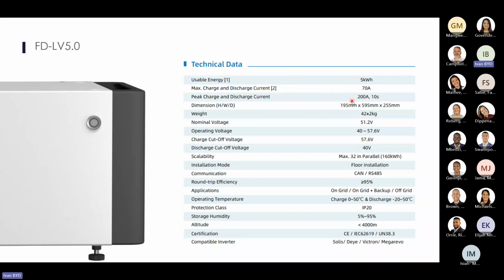So that means on your low voltage batteries, typically you have to have a minimum battery bank size to have the system working. Typically, you're speaking a ratio between 1 kVA of inverter to about 1.5 kilowatt hours of battery, up to maybe sometimes 2 kilowatt hours of battery. So it's a ratio of 1 to 1.5 or 1 to 2 kVA inverter to kilowatt hours of battery. These you can install almost 1 to 1. So you require a much smaller minimum battery bank starting size, which is very nice.